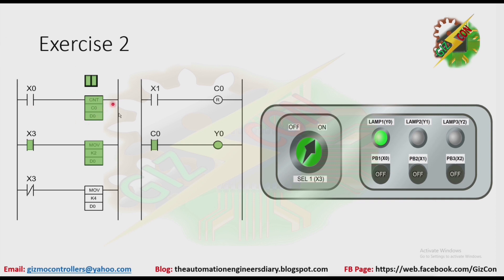After the count of two, the normally open contact of C0 here will be closed, and that will make Y0 to turn on. Now let's press PB2. When we press PB2, X1 will be energized — that will make Counter 0 to reset. Because of that, the normally open contact of C0 here will go back to its initial state, and that will make Y0 to turn off.